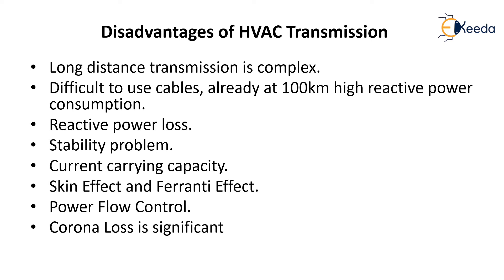Now for the disadvantages of HVAC: when it comes to long-distance transmission, HVAC is very complex and not suitable. The first issue is difficulty using cables — already at 100 km there is high reactive power consumption and reactive power loss, which causes stability problems and reduces current carrying capacity. We also have issues like the skin effect and the Ferranti effect. Because of the skin effect, the effective resistance of the conductor increases, reducing current carrying capacity and power transfer capability.